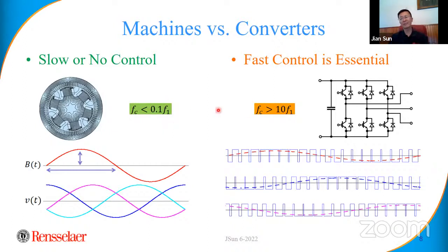So the innermost function is to regulate the current and to give you the sinusoidal response, because you don't produce this sine wave like we do in a generator, right? This is all done by semiconductor switching, pulse width modulation. Your modulating has to be much faster than the fundamental frequency. To make it simple, the control bandwidth of the inner loop in power electronics is about 10 times above the fundamental, right? So you put these next to each other. One is less than 10% of the fundamental. The other is 10 times higher than that. And basically you have 100 times difference in the speed of control.